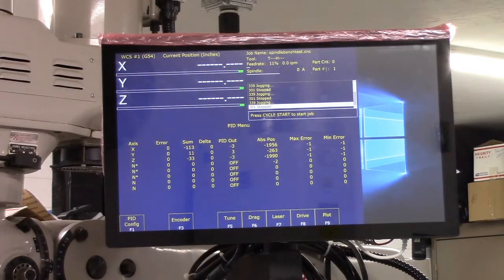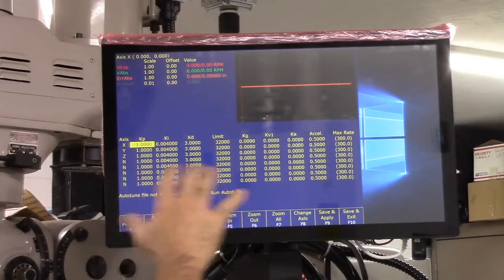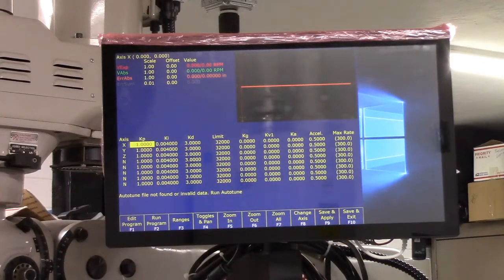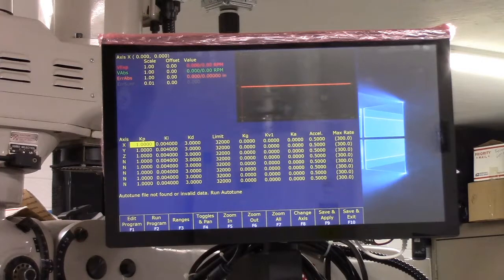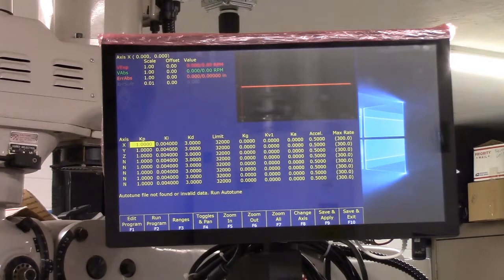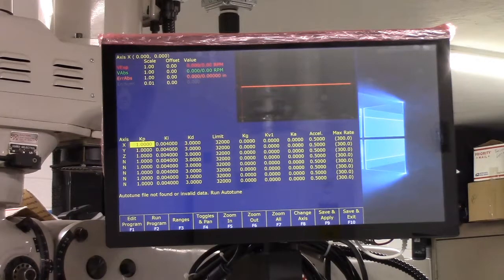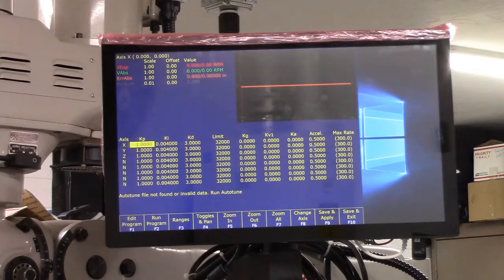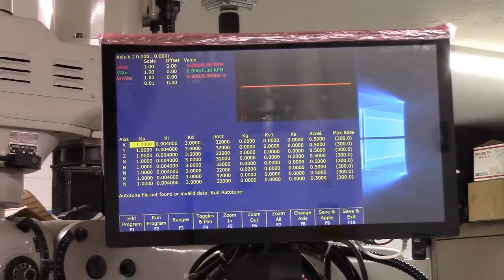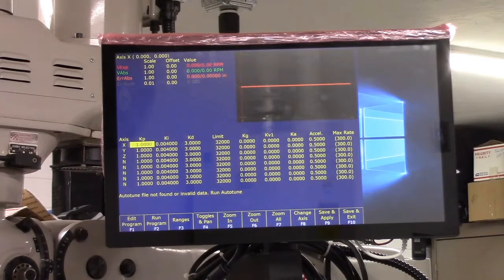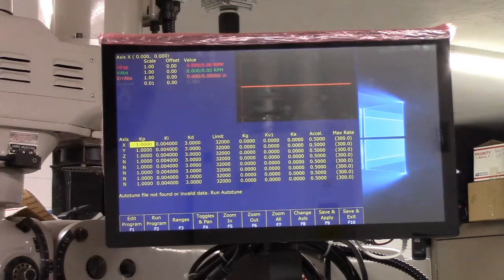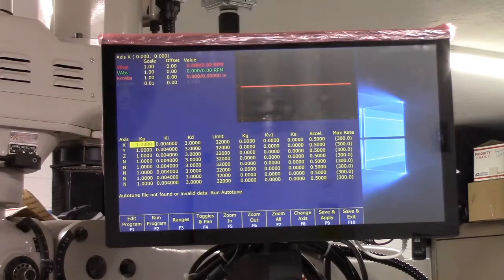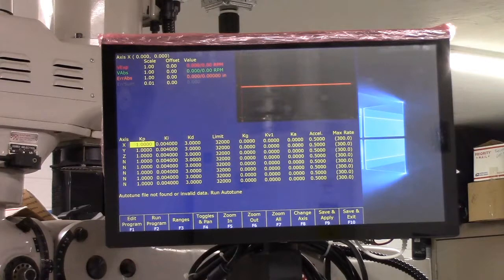Then we go to F4 and then F1, and here's where the baseline PID settings go in. I was fortunate enough, as I previously mentioned, that I had some starting points. The values came right out of the all-in-one DC installation guide, so I was able to check them. They actually from default, the software already had them and they matched up, so that seems to be working because the motors are holding steady for now.